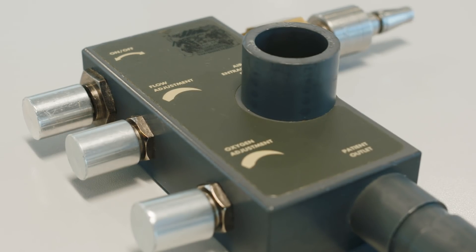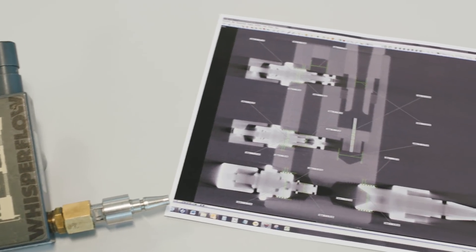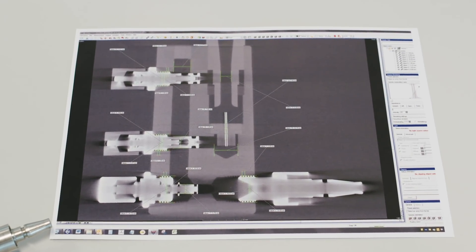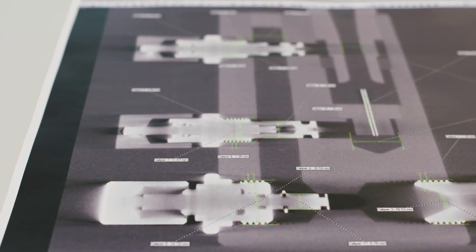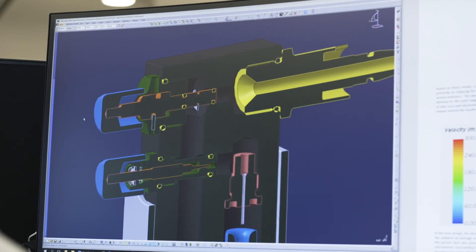This is the device we bought on eBay — a £50 purchase. We got a CT scan of it straight away, which showed us the inside details and helped us take dimensional information from it. This gave us our first insight to the device we needed to make. The key message from UCL to get medical approval was: copy something that already exists. So our whole focus was to copy it exactly — let's not be clever, let's just copy it to gain the original medical approval.